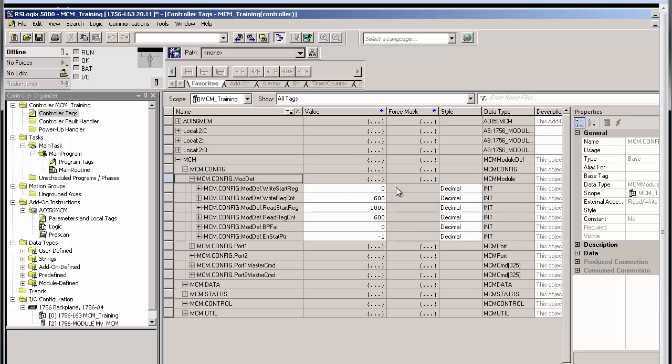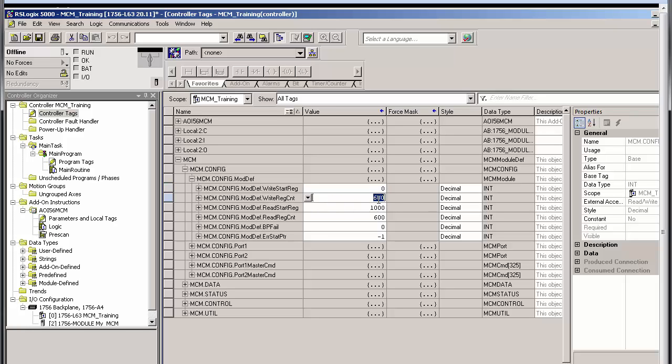The write-start register defines where, within the MCM's database, the write data from the ControlLogix CPU will begin. In this example, the data will start at zero, so that would be the very first register of the entire database. The write-register count parameter specifies the number of registers that will be allocated to the write data from the ControlLogix CPU to the MVI56E MCM. In the example, the count is set to 600 registers.